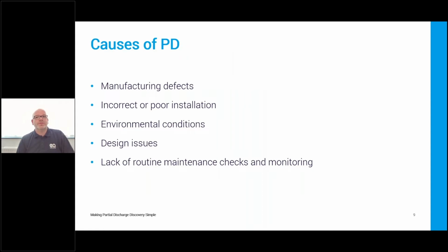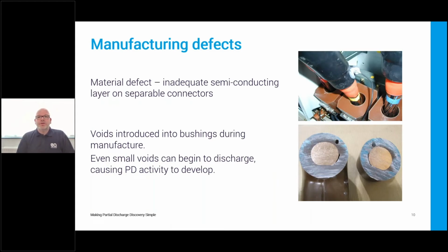Okay, so we'll move on to the second topic now, which is causes of PD. Why does it happen? Well, a few reasons. We'll touch on a few of them. Manufacturing defects, imperfections within the insulation of cables, the terminations, whatever. Poor or incorrect installation, environmental conditions, so the conditions within the substation, design issues, and lastly, and this is not necessarily what causes PD, but it's certainly what can make PD get worse once it develops, and that's a lack of routine checks or monitoring.